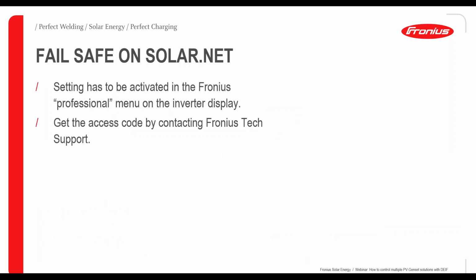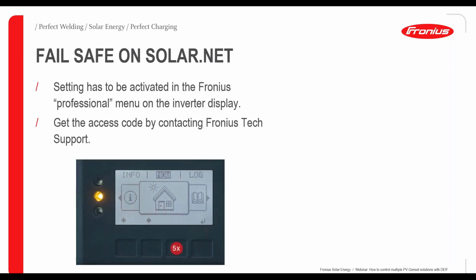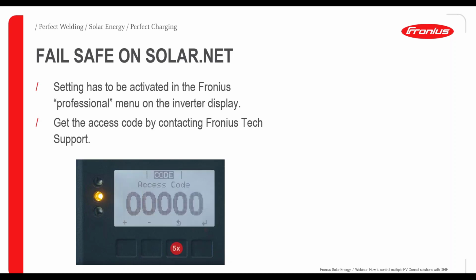So yeah, then there is the topic with solar net ring. Same but different, of course. This time we aren't able to do this on the web UI. Now we have to set it on the display of the inverter itself. On the inverter display itself, we have the option to enter a service code, let's say. There are 4 buttons down below, and by pressing the third one from the left-hand side 5 times, we can enter then an access code.